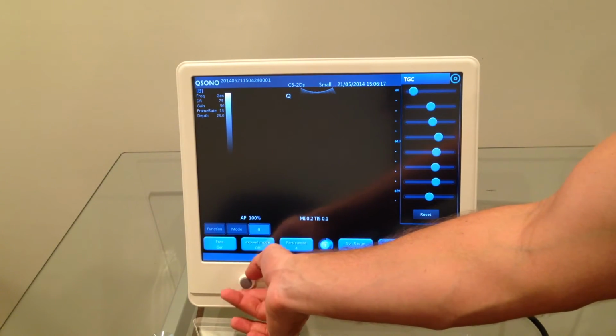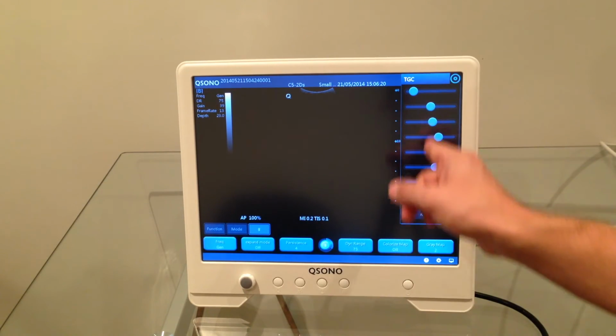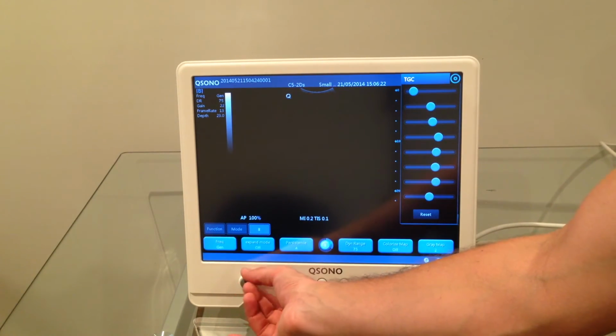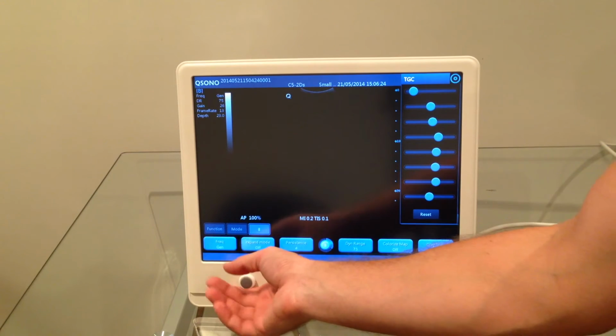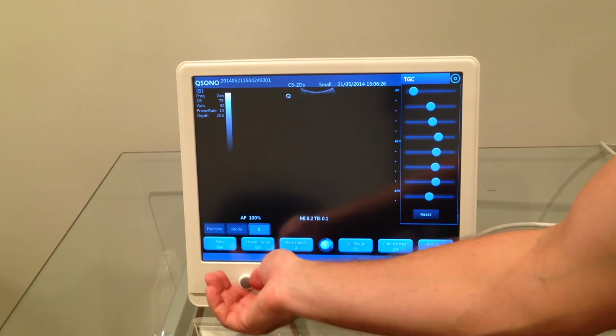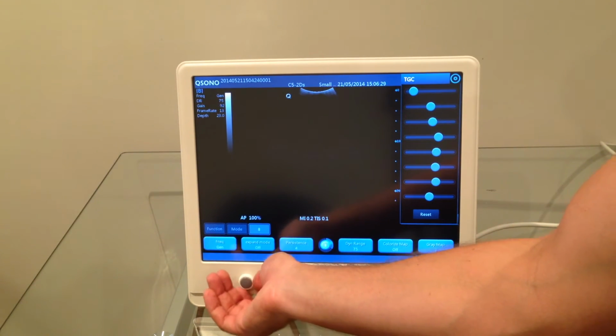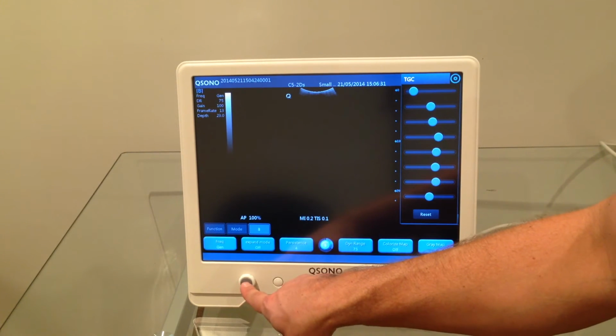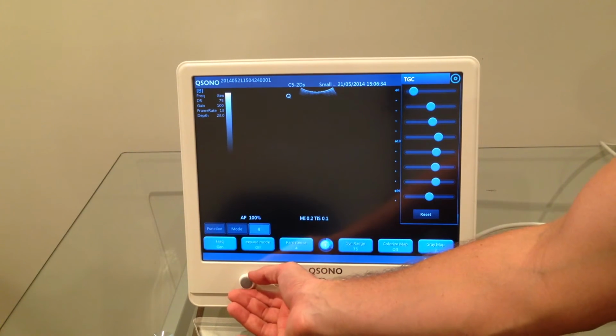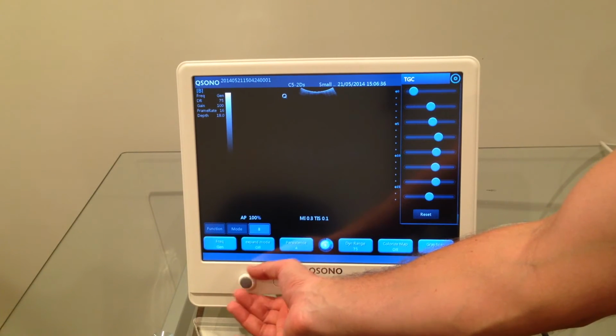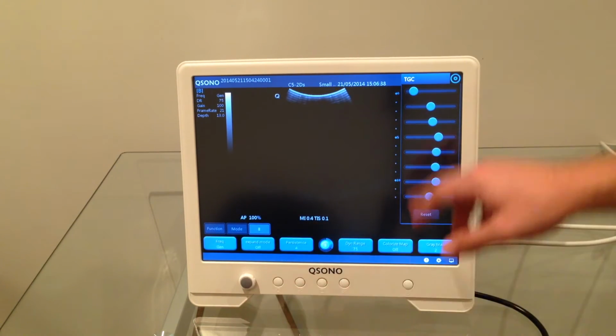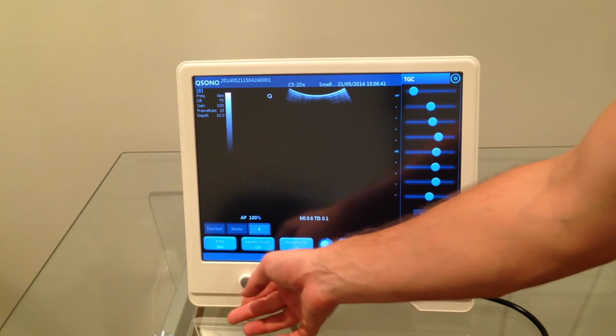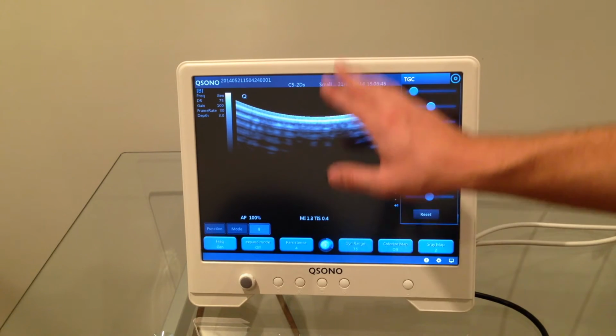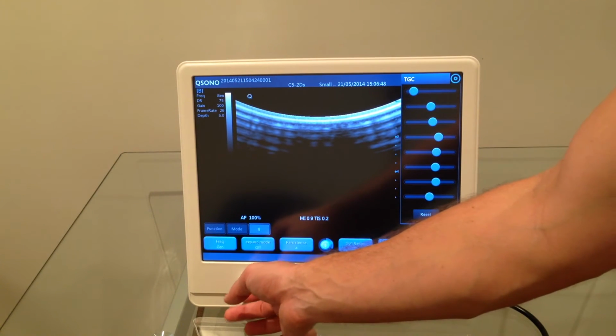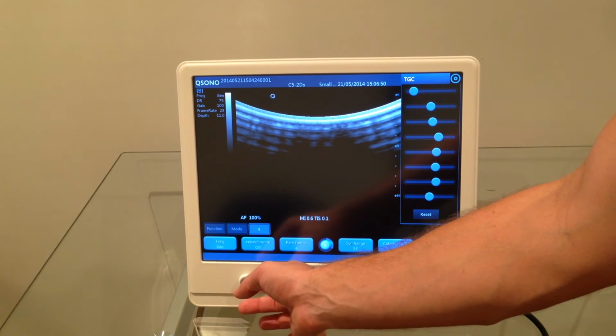At the same time, while the time gain compensation is being adjusted, we can continue to use the knob to change the gain of the image. By clicking the button in again, we can then change the depth of the image. Our unit can go as shallow as 3 centimeters with the convex probe or 1.5 centimeters with the linear probe. And it can zoom out as far as 25 centimeters with the convex probe.